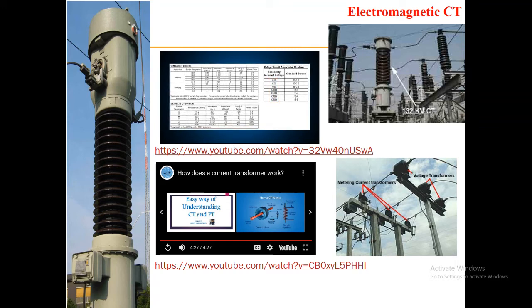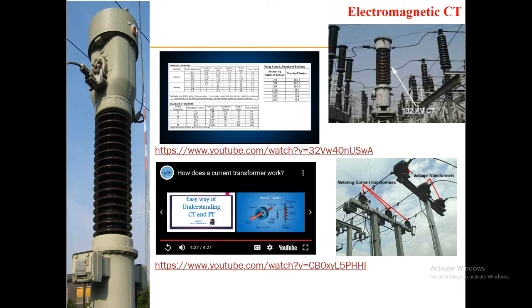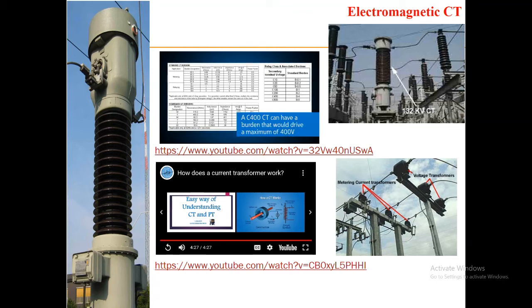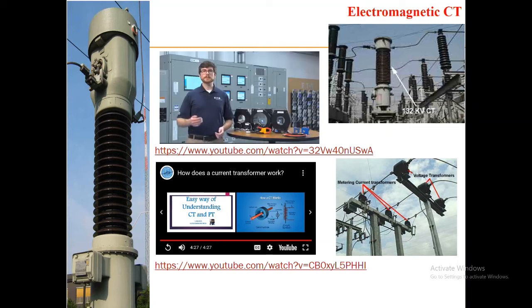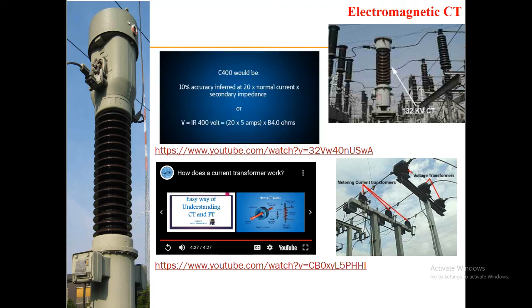CTs come in a variety of accuracy classes. For example, the ratio of primary to secondary current error of a class 1 CT is 1% at rated current. A 0.5 rated CT is 0.5% or less. The accuracy of these devices is very important for protective relaying and metering. They have specific requirements for overload currents in excess of the normal rating to ensure accurate performance of the relays during system faults.